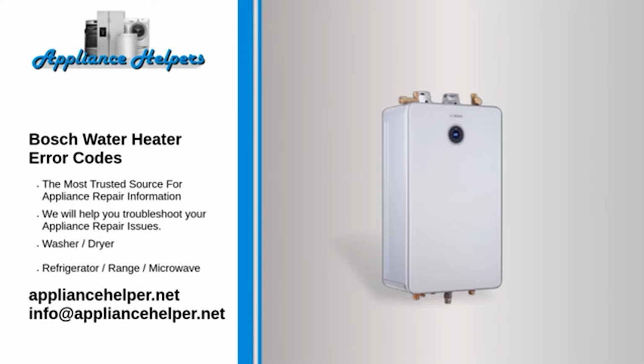Code CA. Problem. Excessive water flow. Fix. Make sure that the water pressure is less than 150 psi and the flow rate is below 10 GPM. Check the wire connections on the water valve and control panel. Code E1. Problem. Extremely high temperature. Fix. The temperature detected by the outlet temperature sensor is over 185 F. Ensure that the sensor is working correctly, and the wire connections are not loose. Another reason for the high temperature is sediment build-up, so descaling is needed.